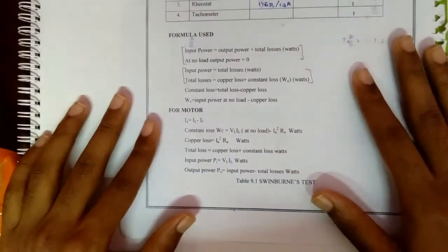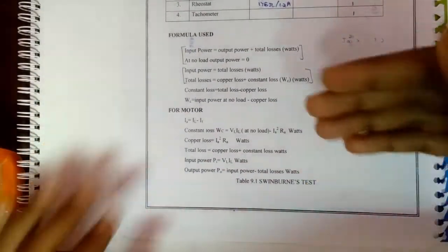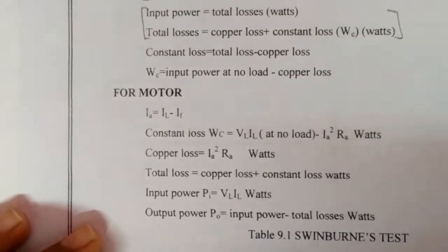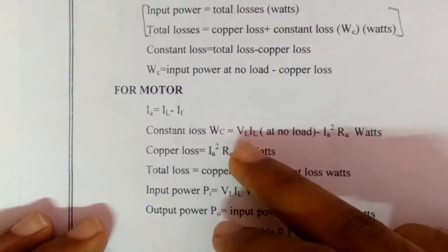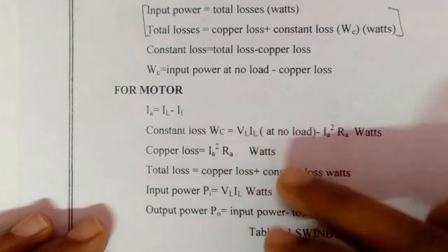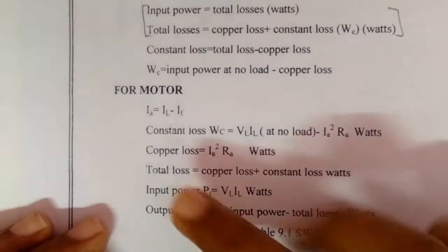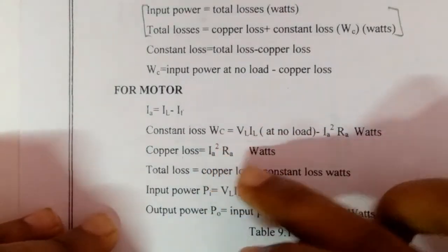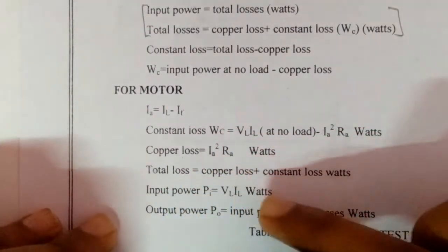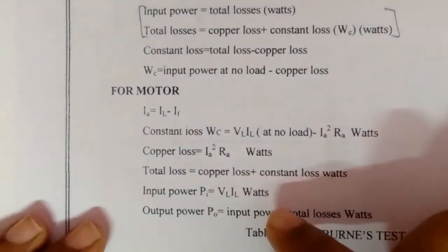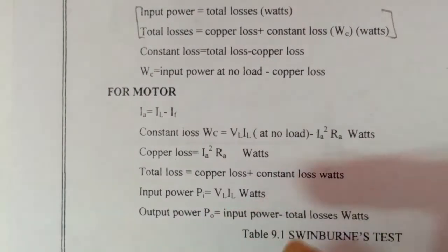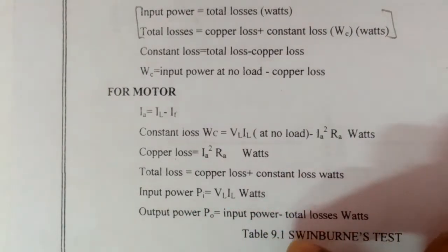Before moving to the tabular column, we should know some formulas used in this experiment. For a motor: armature current IA equals IL minus IF. Constant loss WC equals VL × IL at no load minus IA-squared × RA. Copper loss equals IA-squared × RA. Total loss equals copper loss plus constant loss in watts. Input power P equals VL × IL watts. Output power P0 equals input power minus total loss watts.